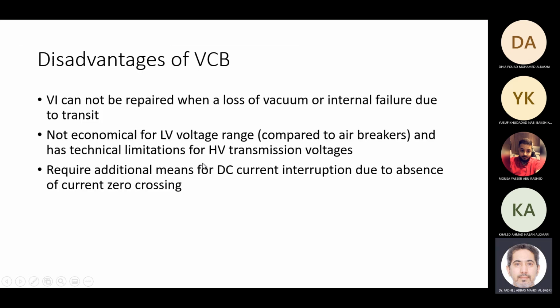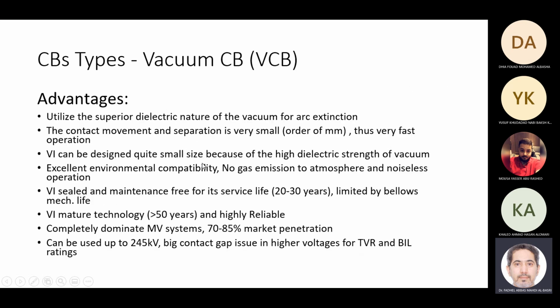Normally they stay in service for 20 to 30 years. This technology is very mature. It's been in the market for more than 50 years and has very high reliability, and represents almost 80% of the low voltage and medium voltage markets. Most of the breakers are vacuum circuit breakers nowadays. And they can be used up to, let's say, 245 kV.